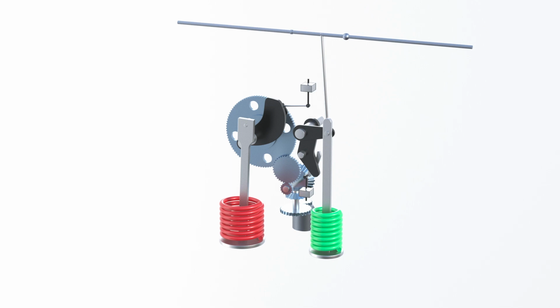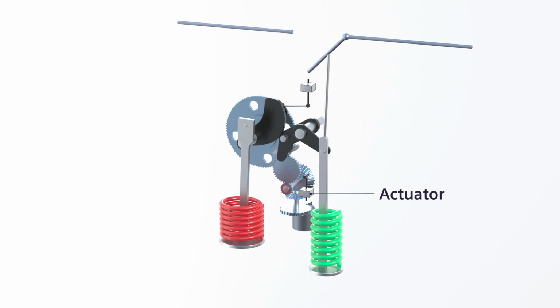Upon completion of the closing cycle, the closing spring is recharged automatically by the electric charging motor. The circuit breaker is now in a normal operation mode. The energy stored in the springs ensures the switching sequence open, close, open at any time and without the assistance of an electric motor.